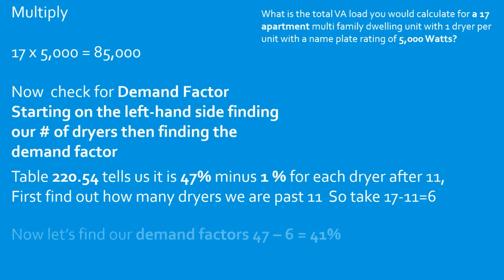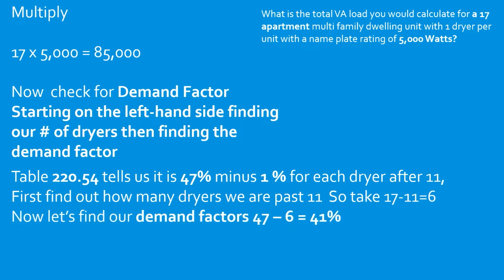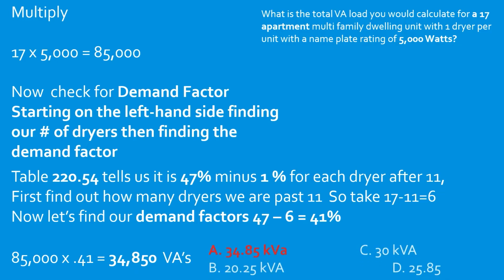So what we do now is take our starting demand factor of 47% and subtract that 6, and that's going to give us 41%. Does that make sense? We started with our base percentage, we found out how many we were past 11, which was 6 more, so we take our base percentage, minus the 6%, and our new demand factor is 41%. So we take our total VAs, multiply it by 0.41, and that's going to give us 34,850 VAs. And we're going to select A.